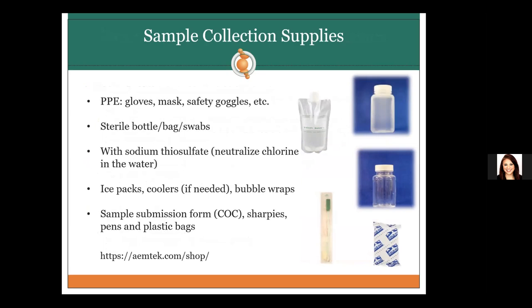For the collection process, make sure to wear proper PPE — gloves, masks, and goggles — and do not contaminate yourself with any water aerosols. Sample using sterile bags, swabs, or bottles that we can provide. Make sure the sampling apparatus has sodium thiosulfate in it, which will help neutralize the chlorine in the water. Store samples in coolers with ice packs if you have many samples. Have bubble wrap ready if you plan to ship them to us. Fill out the chain of custody forms for sample submission and keep plastic bags handy to keep your paperwork dry.